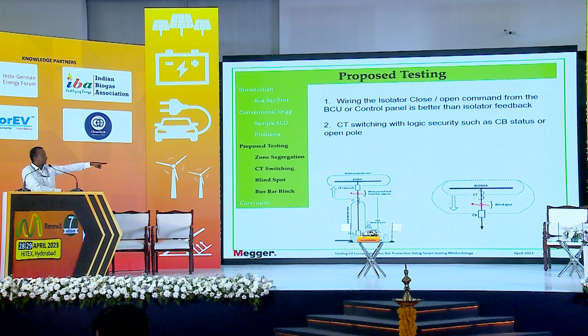So how do we address this situation? With the same concept, whenever the breaker is open, the CT would be removed from the differential calculation. This is the latest concept that we have used, because in earlier days it was the conventional method of operation, with which we have seen multiple maloperations and relays pulling the system out from the grid.